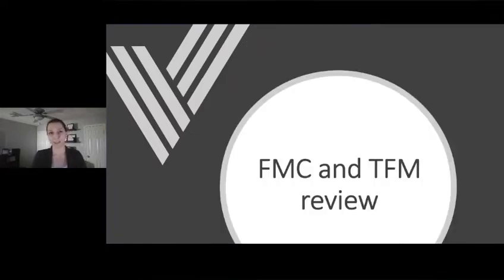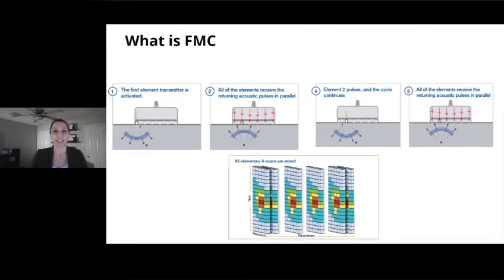But first, a quick review that is always needed for FMC and TFM. So what is FMC? When we talk about it, it's always about the acquisition side of the strategy. The first element of the probe will be firing and then all of the other elements from that probe will be listening or receiving. Then we go to the second element and do the same again until we've covered all the elements. With that, we generate a matrix of elementary A-scans. That's where the name full matrix capture comes from.